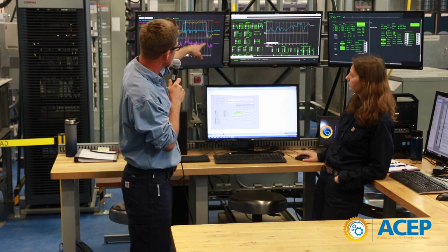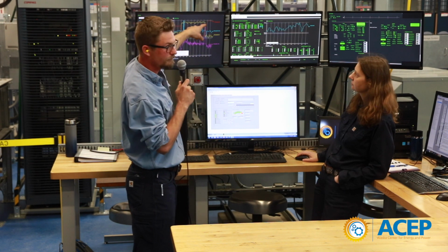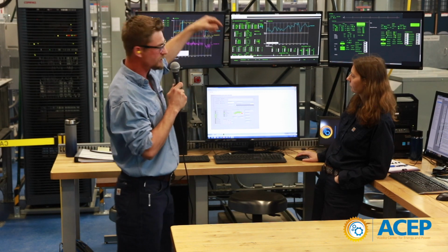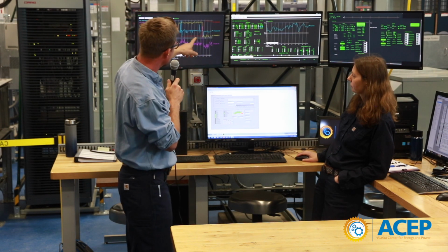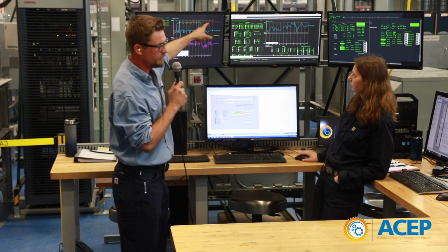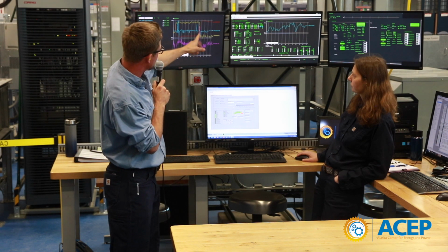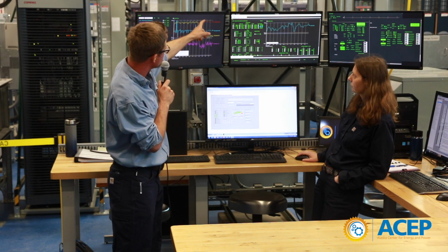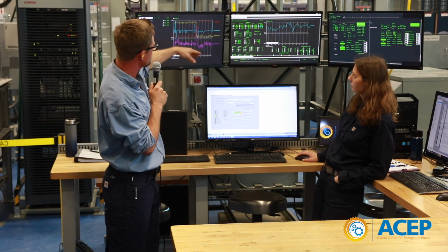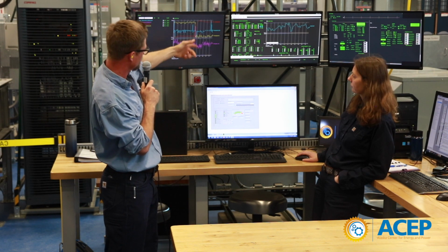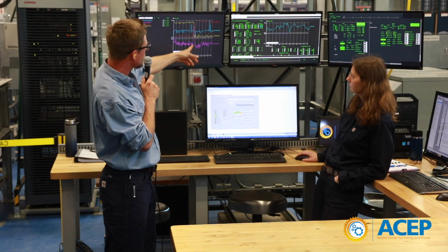Look what happened to our battery, our battery output shot up. That's because when the frequency drops, that means there's not enough power in the grid. This red line is our generator output, so look at the response of the generator. It gradually responds like that to the change in the amount of power, while the battery responds immediately.